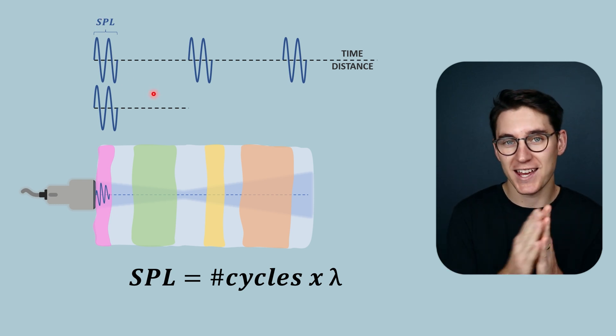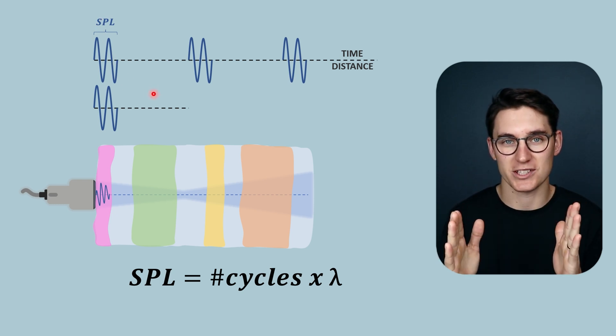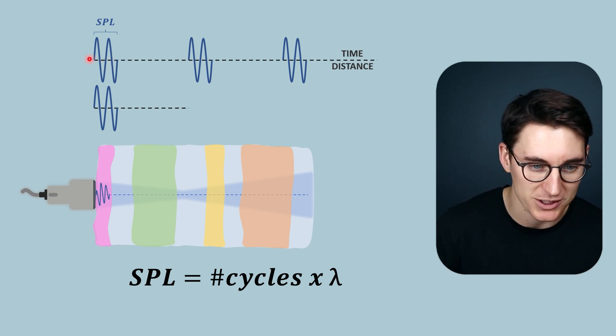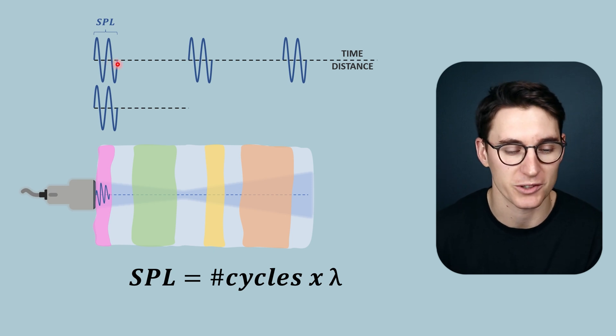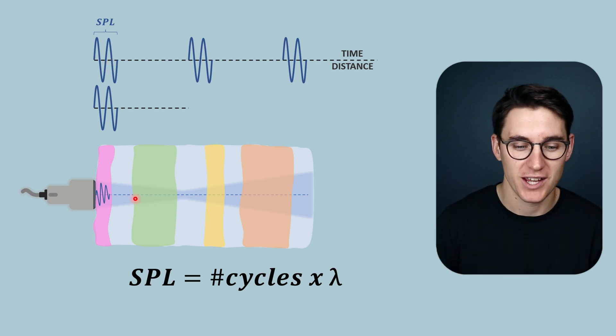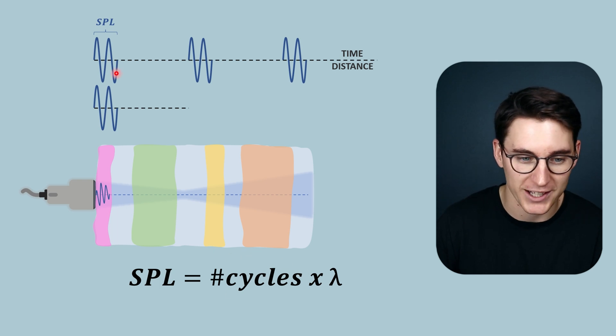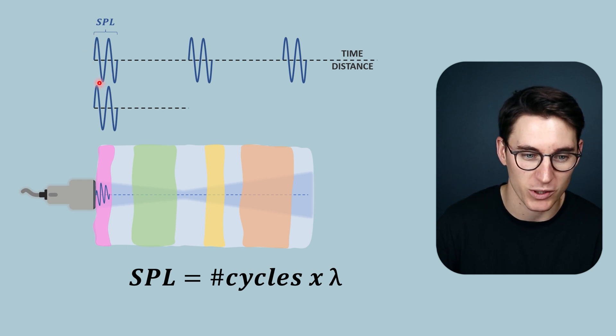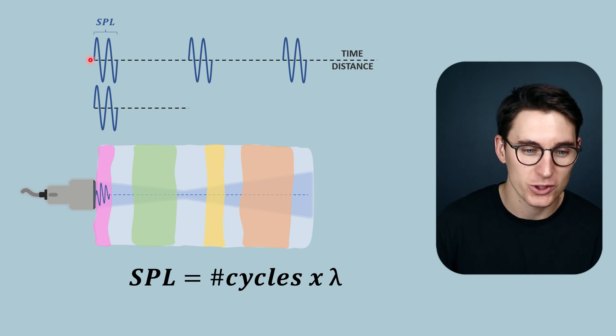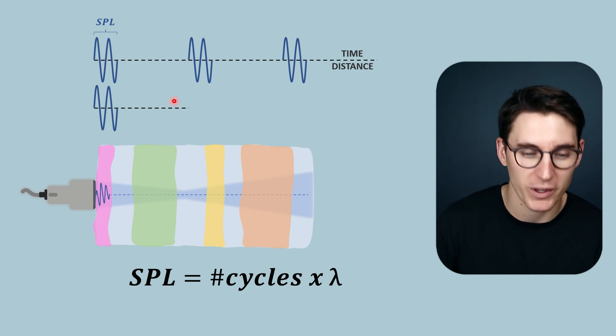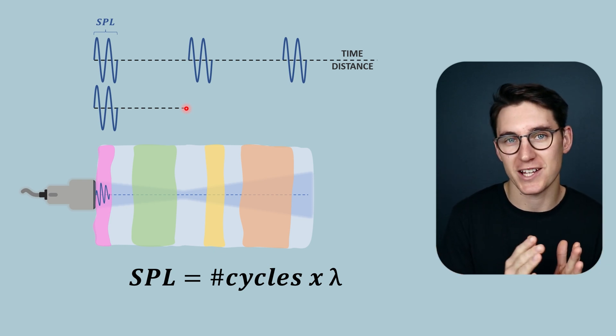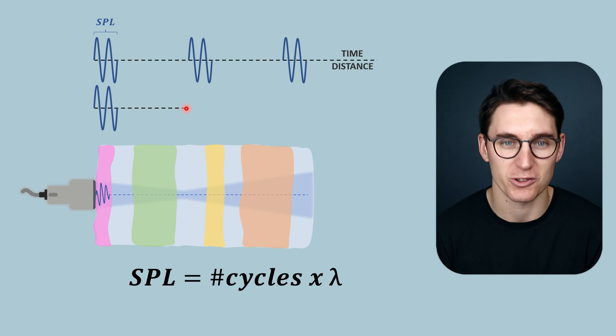The spatial pulse length is the total distance of a single pulse that we send into tissues. The time this pulse takes is what's known as our pulse duration. Our spatial pulse length is a distance measurement: if we take the number of cycles within our pulse — in this example, two cycles — and multiply by the wavelength, we will get our spatial pulse length.